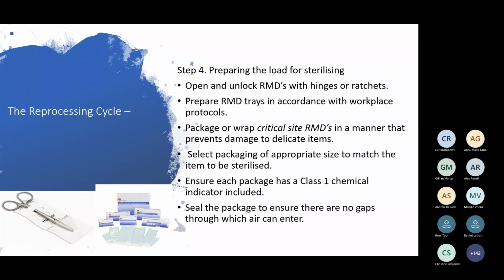Anything with a sharp tip should be in a holder and a protective cover, because they can potentially pierce your bags and put little micro holes in your bags. And if you've got little micro holes in your bags, then your bags aren't going to be sterile. So please always make sure that you prevent damage to the tips and also damage to your packs because of potentially piercing them. Select packaging of appropriate size to match the items to be sterilized.